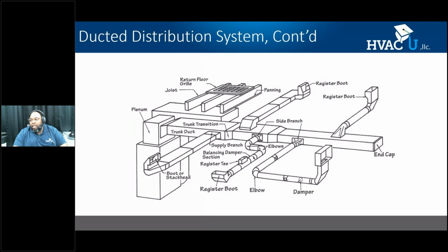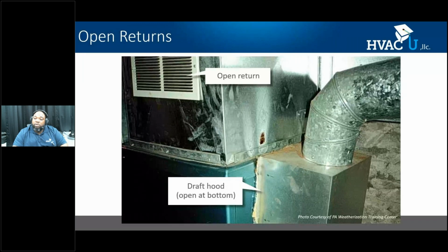All right, so one of the things you want to resolve is open returns. This is something that's pretty critical, especially when it's located by a combustion source such as a draft hood. That can also impact that. That will be things that we look at.